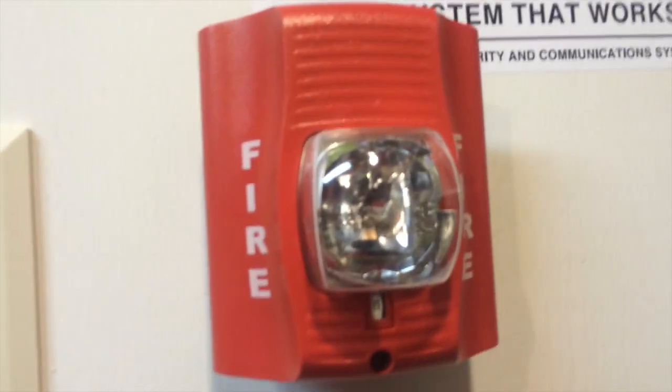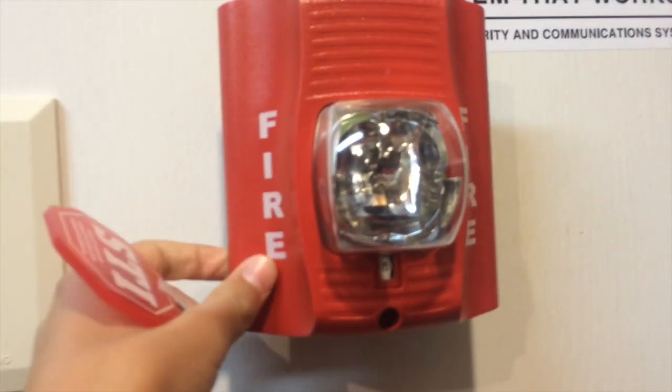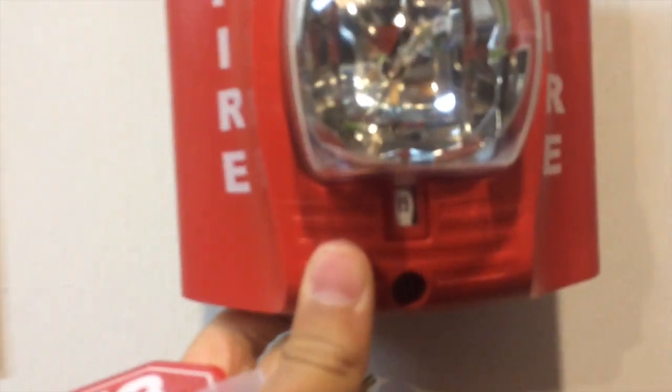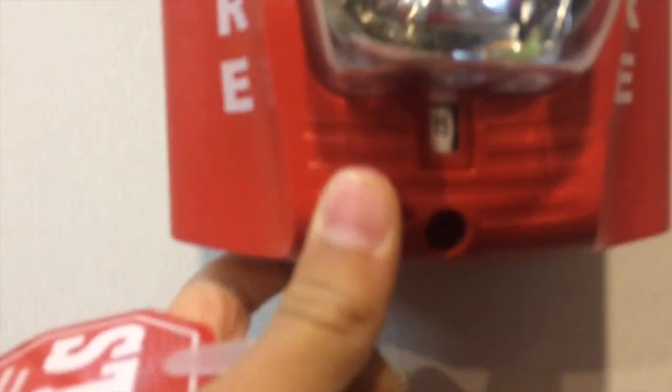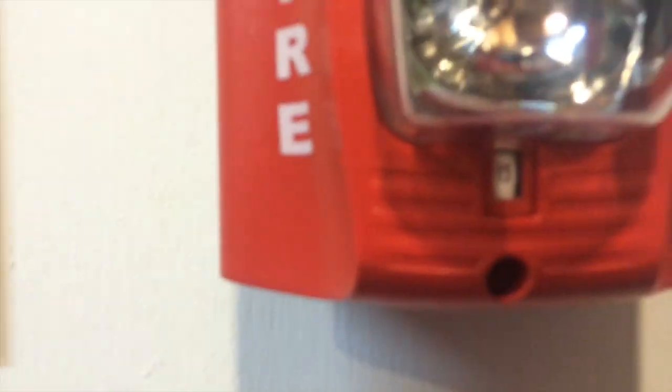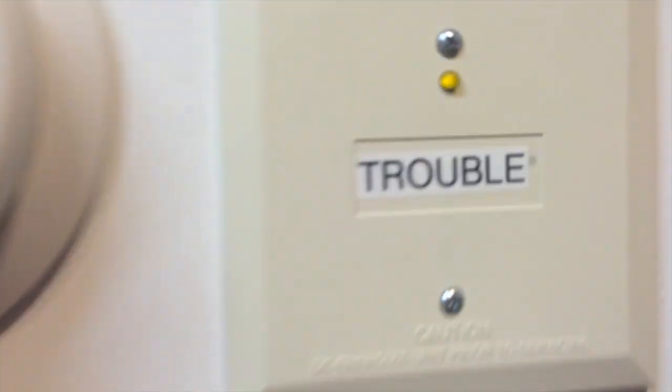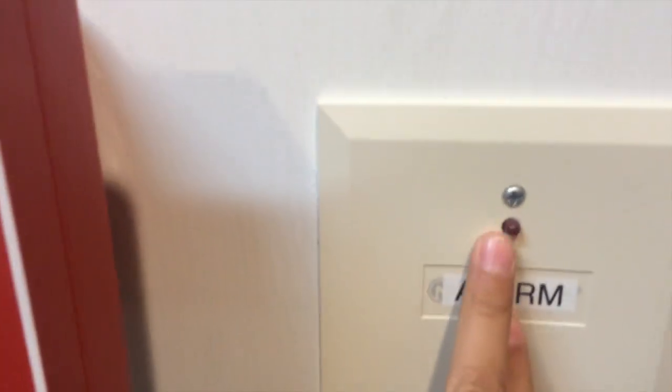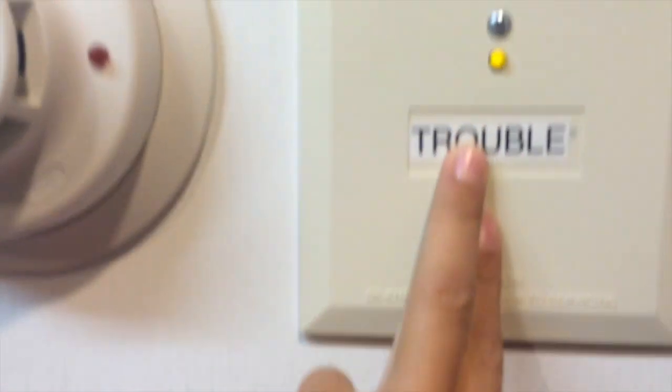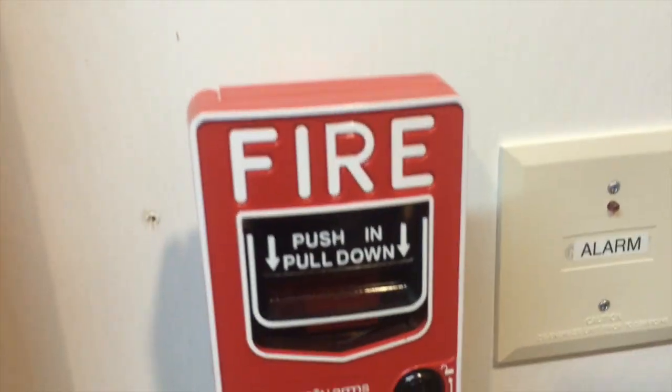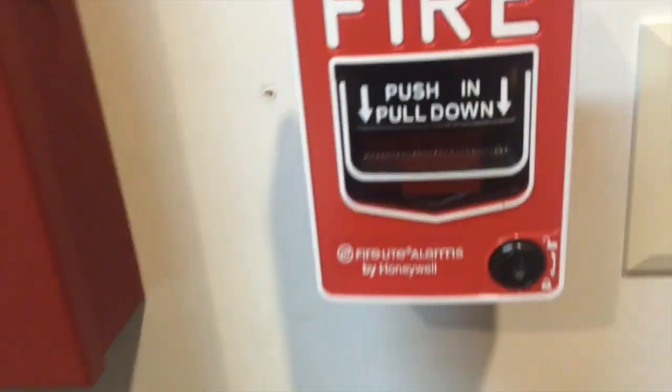Here's my System Sensor Spectre Alert Remote Strobe, set on 15 Candela. The notifiers, this will flash if it's an alarm, and this will turn on if there's trouble. There is a trouble. I just really don't have the batteries in it right now.